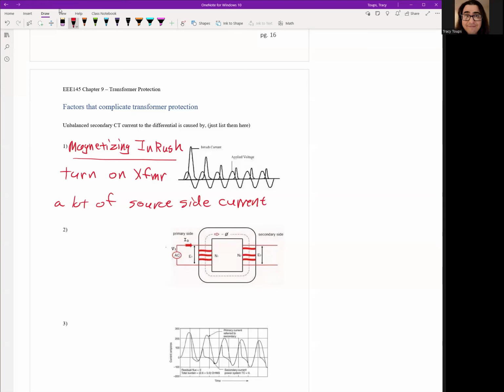Because the load side, we assume, is dead. There's no source in the load. So there's only one direction where the inrush can come from, and so it's the source side, which has some issues with differential protection because you have an unbalanced secondary CT current when only one side is sending current to the transformer. So we're going to have to somehow fix or trick the relay to let the magnetizing inrush in. Otherwise, we'll never get the transformer online because we'll try to turn it on, the inrush will happen, the differential kicks off immediately, and we're just stuck. So we're going to have to figure out something to overcome magnetizing inrush.